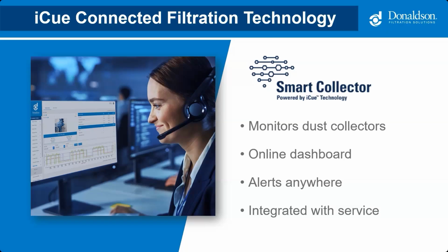It does have a full monitoring online dashboard. There's a picture of it right there on your screen. You can actually view a photo of the actual collectors. You make sure it's set up properly. You can see the performance metrics of your collector. You can also trend the historic performance. A lot of times it's good to look at how your dust collector is performing over time, not just at a moment in time. So that trending is really handy.